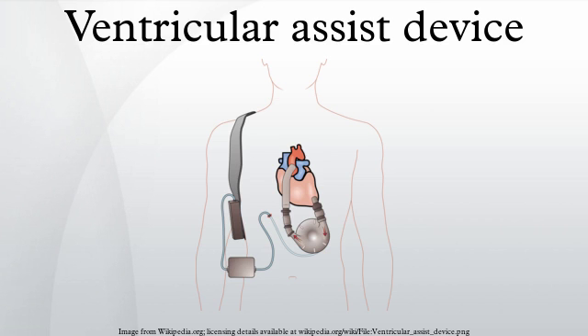Both types have a central rotor containing permanent magnets. Controlled electric currents running through coils contained in the pump housing apply forces to the magnets, which in turn cause the rotors to spin. In the centrifugal pumps, the rotors are shaped to accelerate the blood circumferentially and thereby cause it to move toward the outer rim of the pump, whereas in the axial flow pumps the rotors are more or less cylindrical with blades that are helical, causing the blood to be accelerated in the direction of the rotor's axis. An important issue with continuous flow pumps is the method used to suspend the rotor.